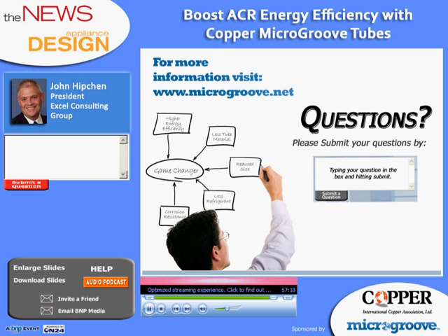What is the status of the development of air conditioners with smaller diameter copper tubes among the OEMs? It is being used quite heavily in China, and as we mentioned, a lot of this work was done in China, where a considerable amount of air conditioners are manufactured. So the status is that this trend is seen quite readily in China. It's starting to be seen in North America as well. The typical 3/8" 9.52 millimeter tube is still quite common in North America, but we are starting to see manufacturers switch to smaller diameter tubes for exactly the reasons that we presented today.